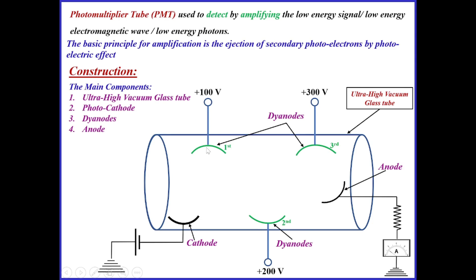So we have the cathode and three dynodes: the first dynode at positive 100 volts, the second at 200 volts, the third at 300 volts. The last electrode is the anode, which collects the high-speed, high-flux electrons and the signal is detected by the ammeter.